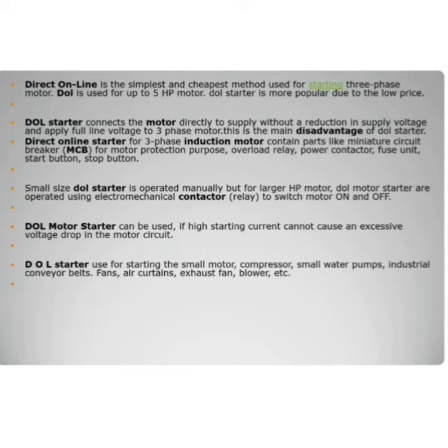The DOL starter connects the motor directly to the supply without reduction in supply voltage and applies full line voltage to the 3-phase motor. This is the main disadvantage of the DOL starter. A direct online starter for a 3-phase induction motor contains parts like circuit breakers for protection purposes, overload relays, power contact switch, start and stop push buttons, fuses, etc. Now I am going to show you the diagram and the parts involved.